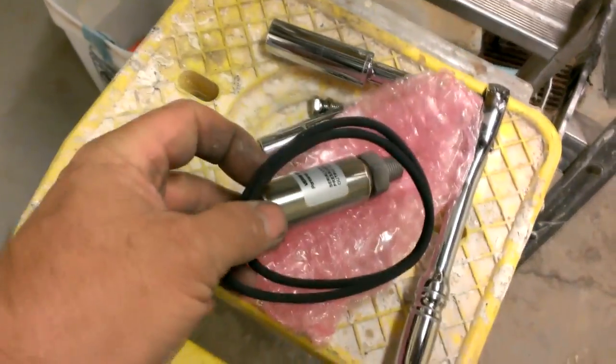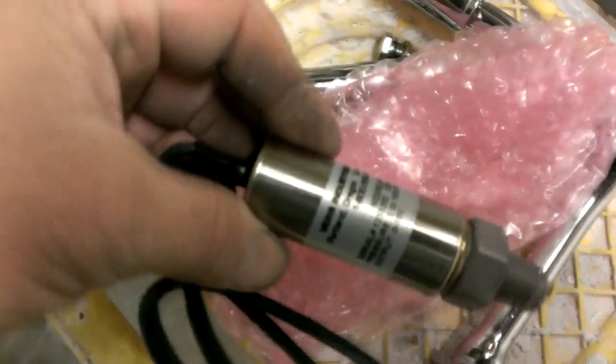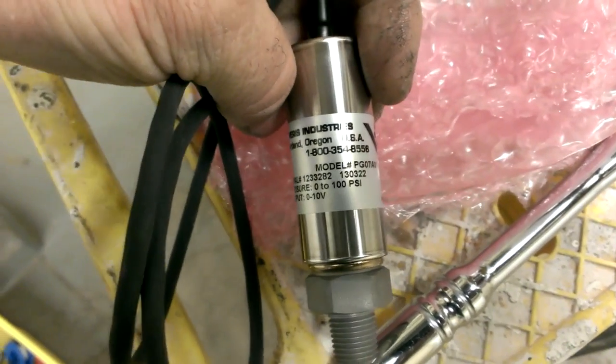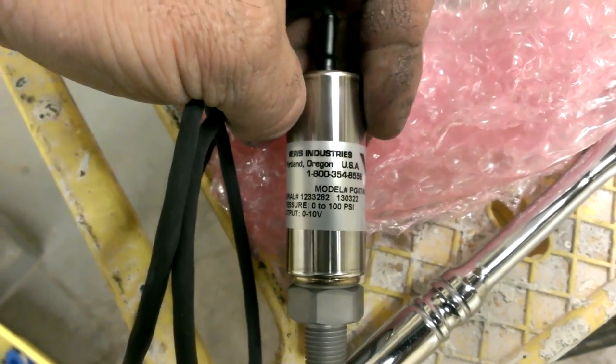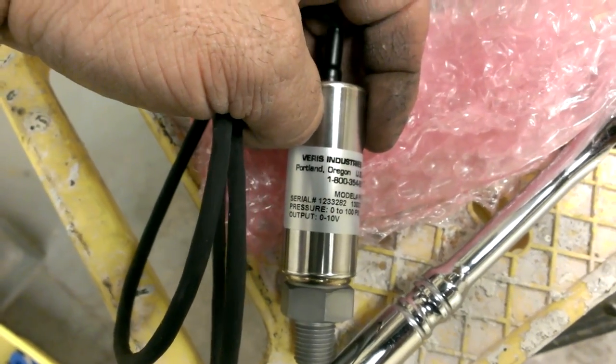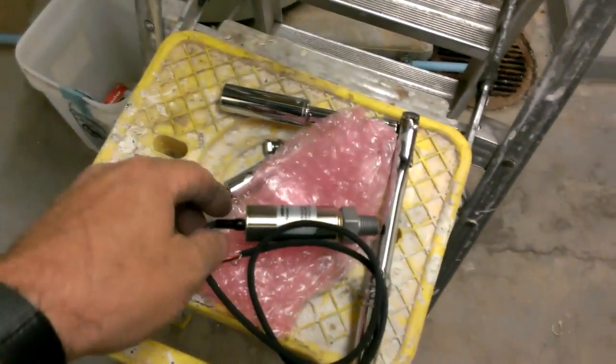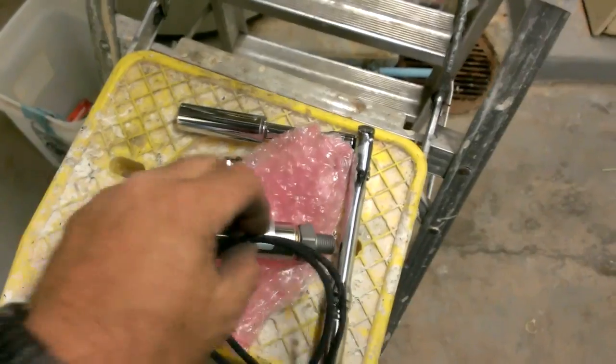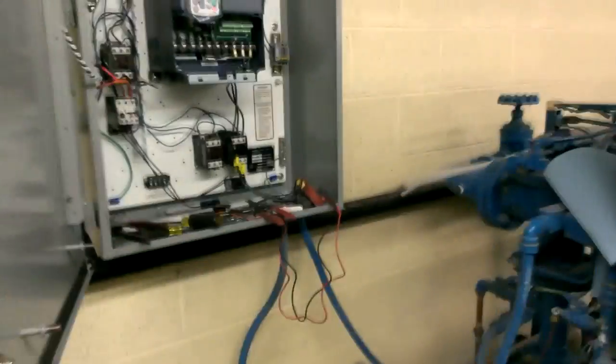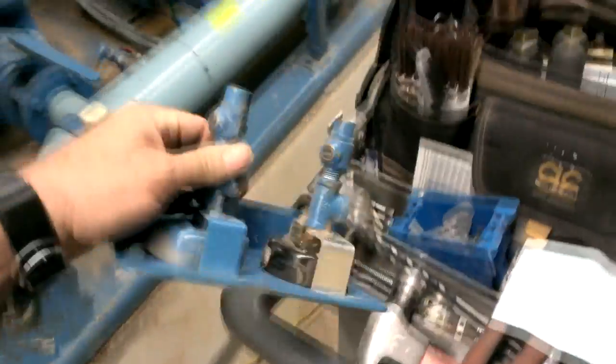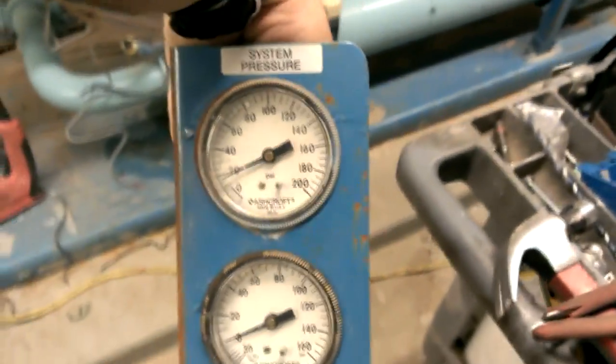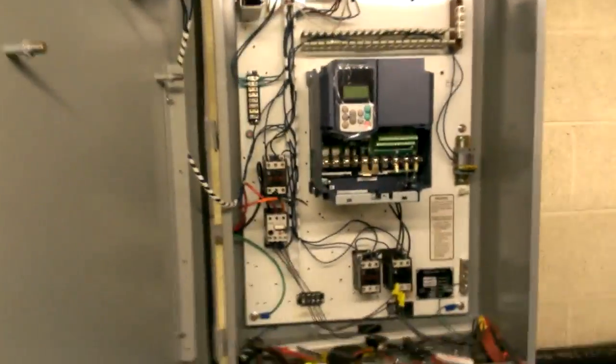Just got this shipped when you've seen this today. Zero to 100 psi, zero to 10 volt. It's going to get the feedback to the Fuji VFD. And that's just getting ready to mount the system pressure gauges. I'm going to put that over here on the side and run a line to it and also screw in the transducer right there. And then that'll control the pump.